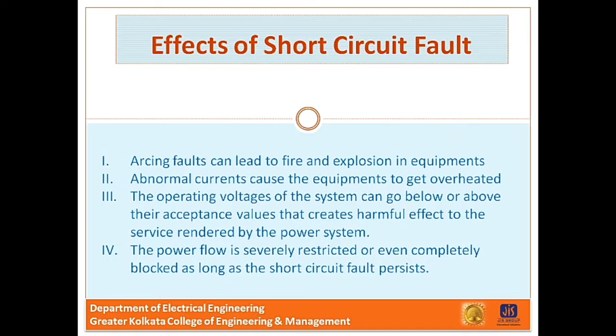So these are the effects of short circuit fault, and our aim is to remove the faulty area from the healthy portion of the power system as soon as possible. So for this reason we are using some protection devices. When a fault occurs in any part of the system, it must be cleared in a very short period to avoid greater damage, as I told you in the previous slide. The fault clearing system uses various protective devices such as fuse, relay, circuit breaker and lightning arrestor. Now we discuss one by one.